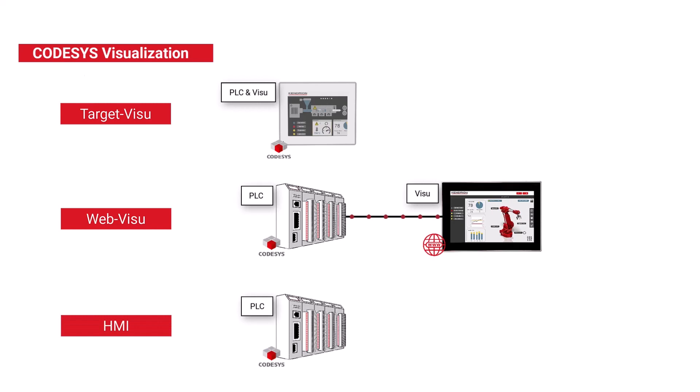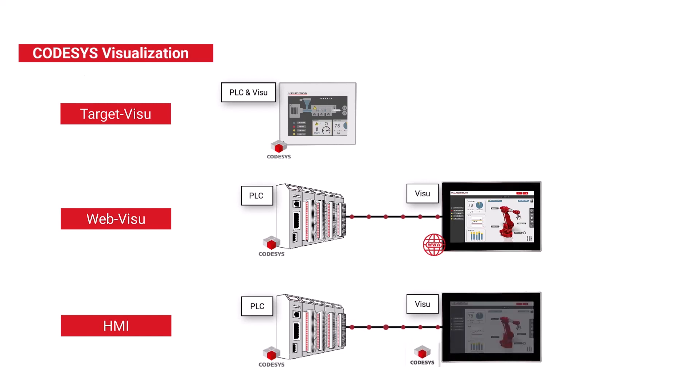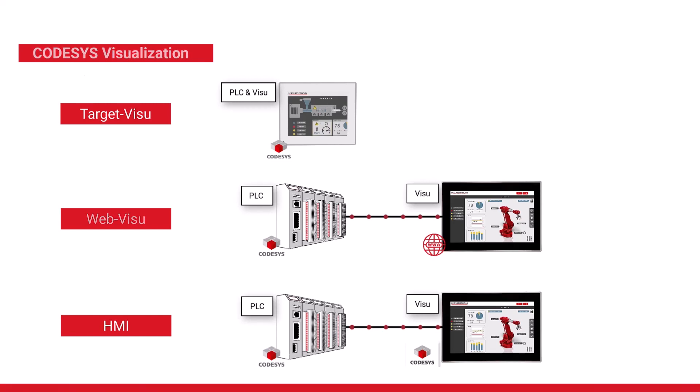As with web visualization, the controller communicates with the VisU via a LAN connection, but instead of a browser, a special CodeSys runtime system handles the visualization. This means that the image buildup takes place completely on the HMI device and thus relieves the PLC. Only the data of the visualization must be transferred.